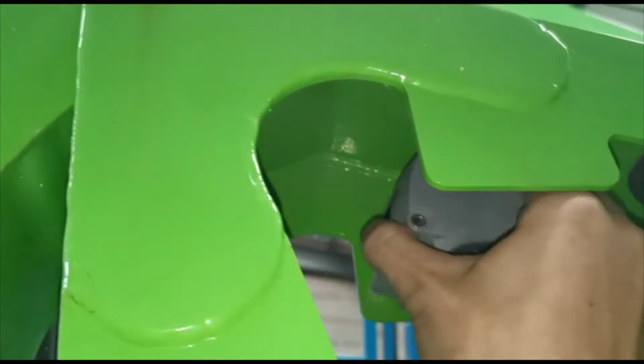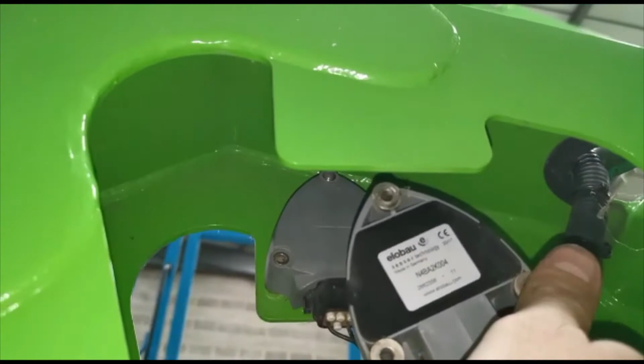Let's take this sensor, number 2. You see? So this one is fitted the wrong way around. So what I have to do is take this off, and it has to be fitted like this. Okay. So that's the way it has to be fitted on. It doesn't matter which one is first. This one could be first, as long as they fit in the same direction, because they're reading the same angle. If they're fitted the other way, they're working against each other. So they have to be fitted exactly the same way, so they're providing exactly the same data.